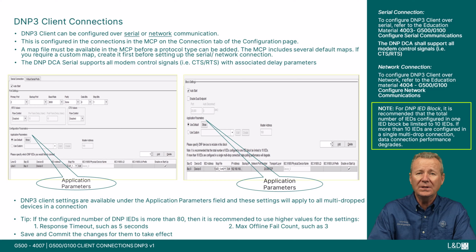Note that for DNP IED block, it is recommended that the total number of IEDs configured in one IED block be limited to 10 IEDs. If more than 10 IEDs are configured in a single multi-drop connection, data connection performance degrades.